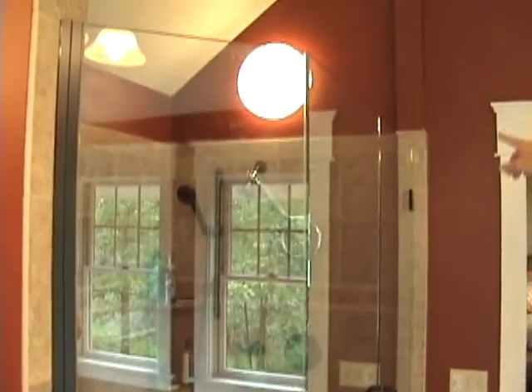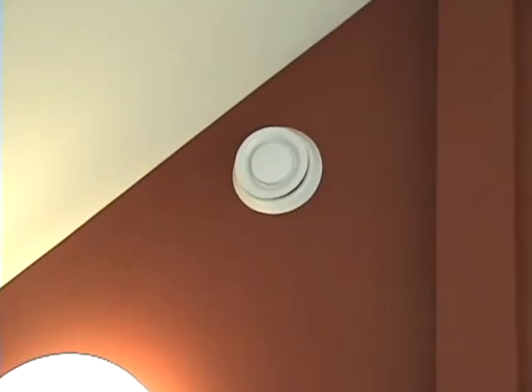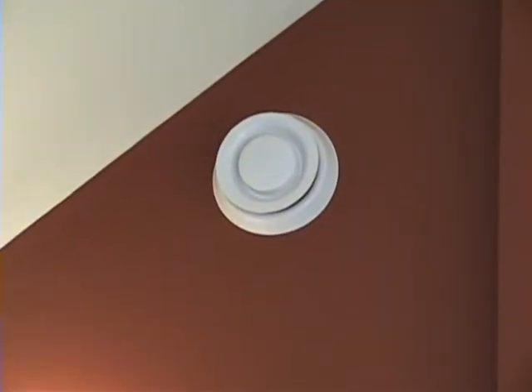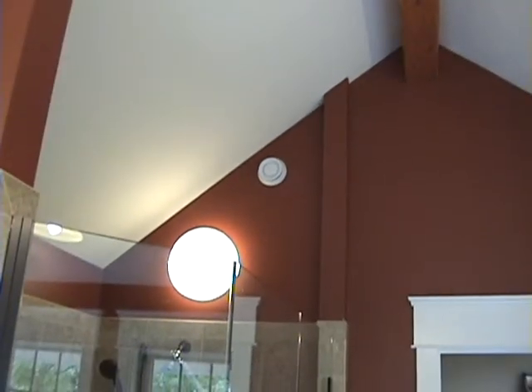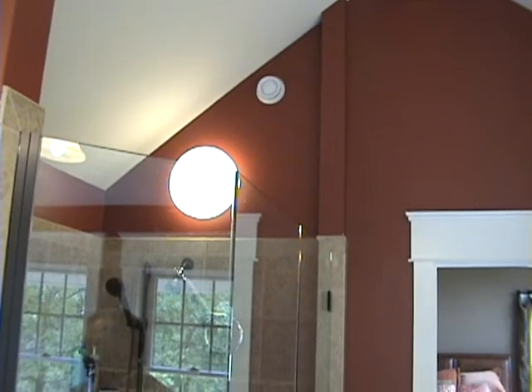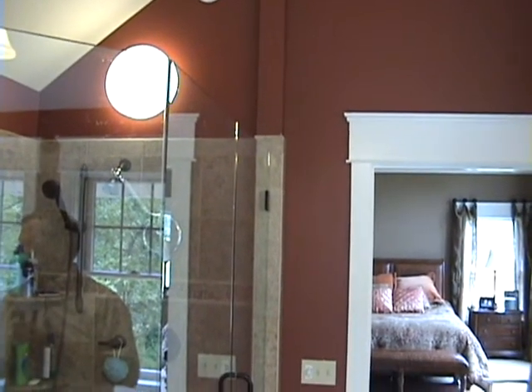If you look high on the wall over the shower, not only do you notice the fluorescent lighting, but there's also a vent up there. We do not have any regular bath fans. That vent is tied to a mechanical ventilation system called a heat recovery ventilator. It allows us to evacuate air from each of the bathrooms — there's also one in the kitchen. So we're constantly taking the stale air out of the house and bringing in fresh air to replace it. In the wintertime, we're taking the heat from the outgoing warmer air and transferring it to the incoming colder air at about 85% efficiency.